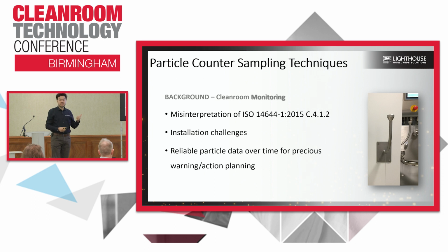And there are installation challenges, as we mentioned, not limited to the machine, but also in the clean room. You have a service area where you will be providing the particle counters, because particle counters being accessible for service is also important. You cannot really hide them within the machine where you will not be able to service them, so that they will be physically available for you if you need to do any servicing, calibration, whatsoever. So this is also a limitation with the installation. And reliable particle data over time for the alarm and action limits means that when you collect particles, you shouldn't lose them within the tubing, so that it will give you a right indication of the status. What if you have direct tubing within the system without any particles available in the field? You just touch the tube, you will see a lot of particles coming out from your tubing, right? I'm sure you have witnessed the same situation several times.